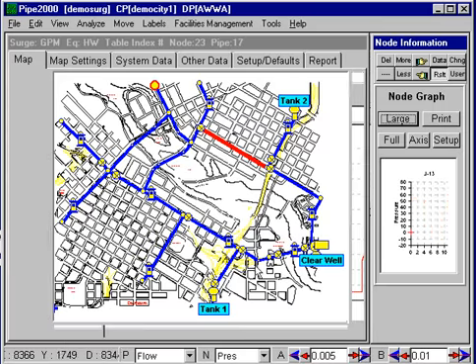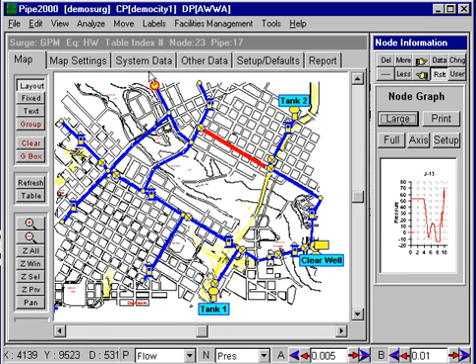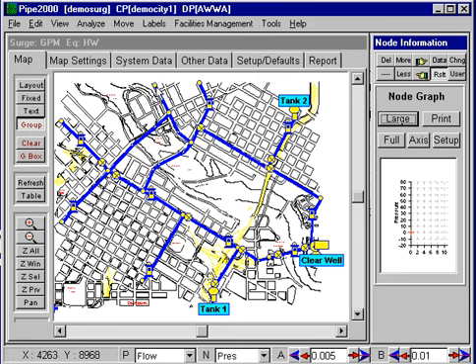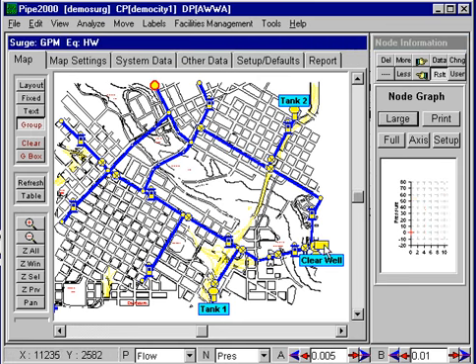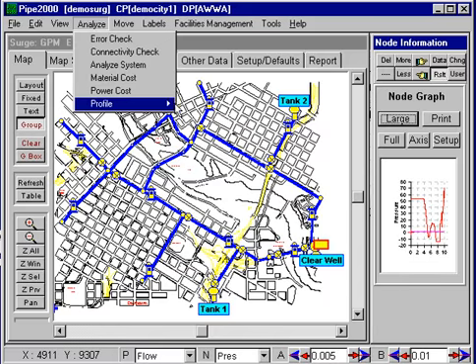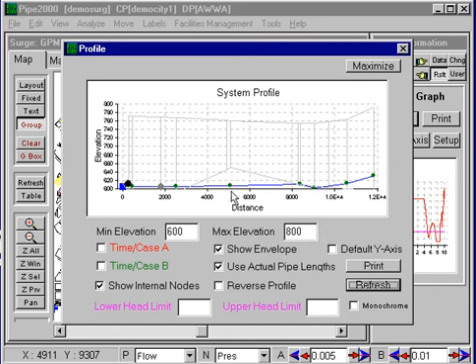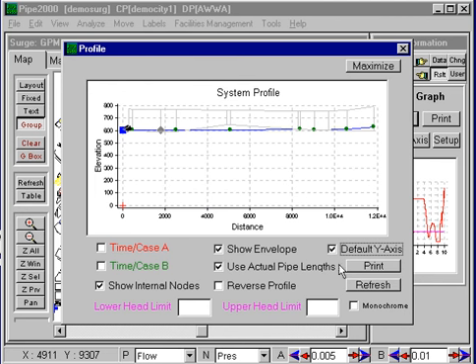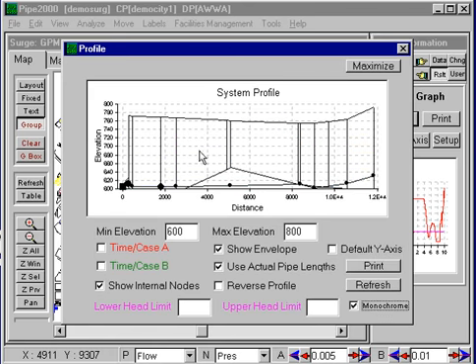Another useful way of looking at the results is to look at a profile. We go into group mode, select a node, and go back to the reservoir to do a profile. We set up the profile and what we see is a pipeline profile and the envelope of pressures. Switching to monochrome makes it a bit clearer. This shows that in some areas the pressure is dropping below the pipeline profile. These profiles are very useful for studying the effects of pressure — this is the path that was taken.